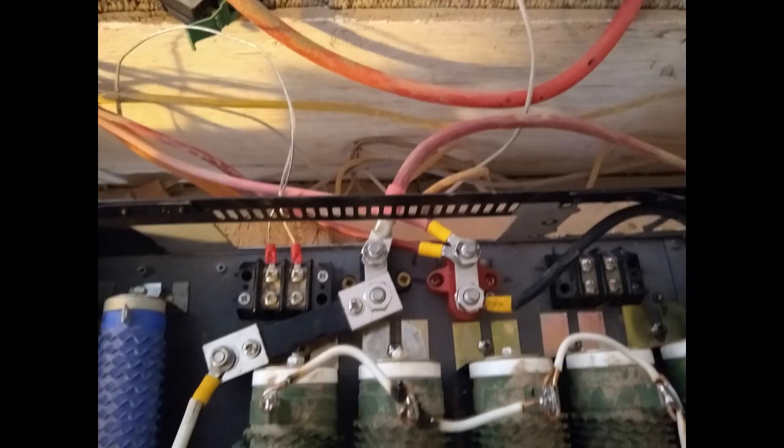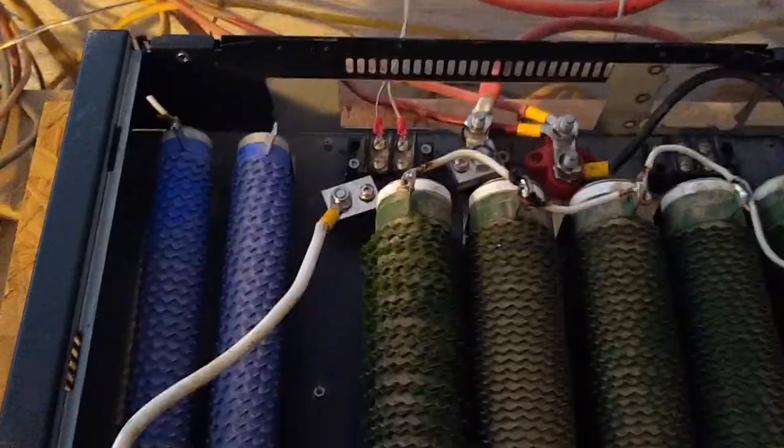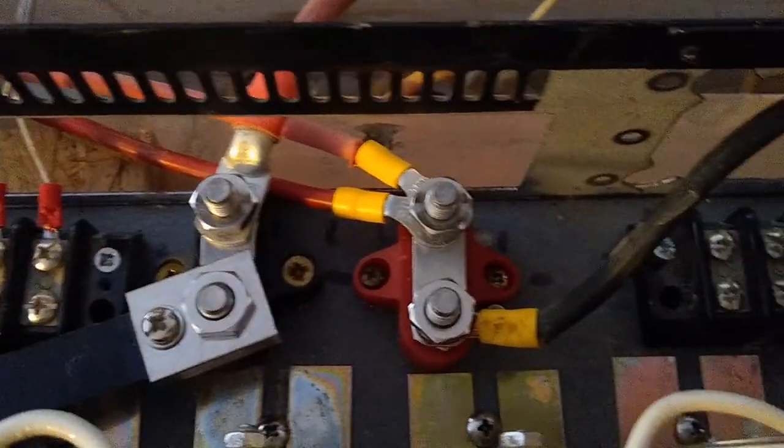You can see I've got the shunt already mounted along with all of the terminal blocks, and everything's wired up and ready to go. The blue resistors on the left are the emergency over-voltage resistors — I can talk about those probably in the next video, but those are not hooked up at this point. The preliminary test here is just to have everything wired up so that the wind turbine can divert through the resistors when necessary, and it's working. I've got the one bad resistor in there just as a placeholder, and when the new one comes in I should be able to just unbolt that one and bolt in a new one.